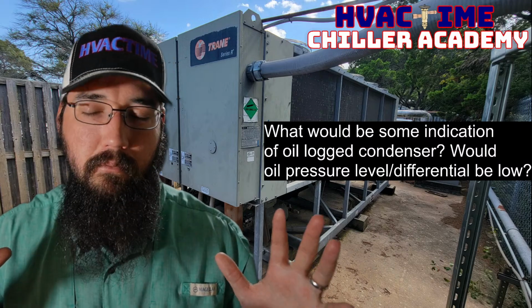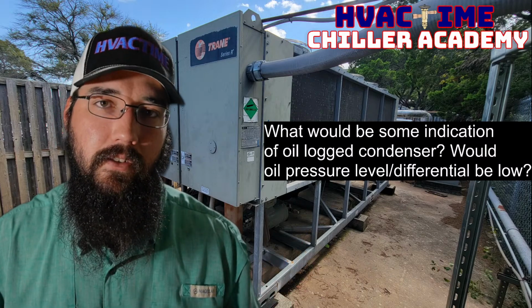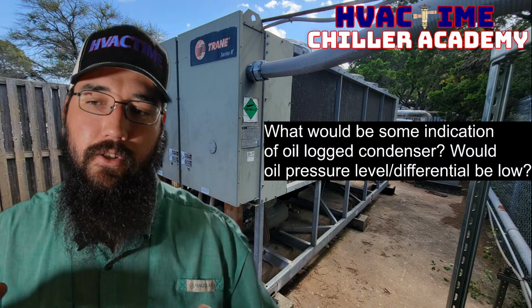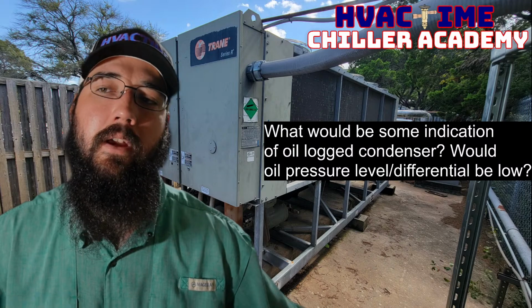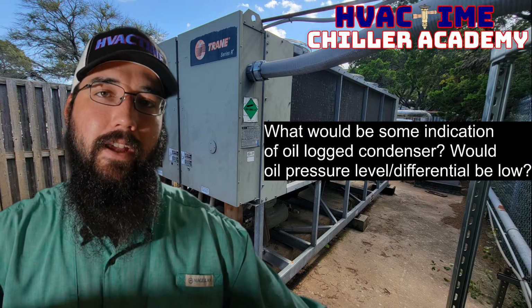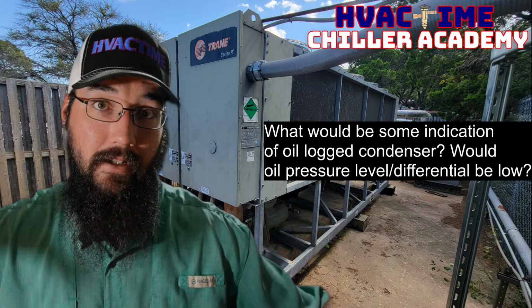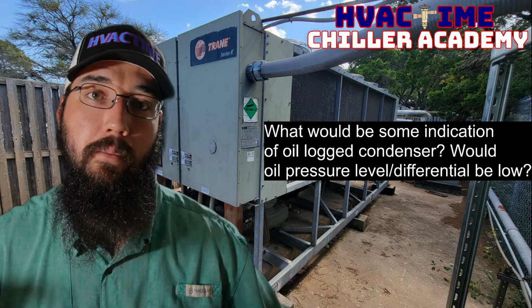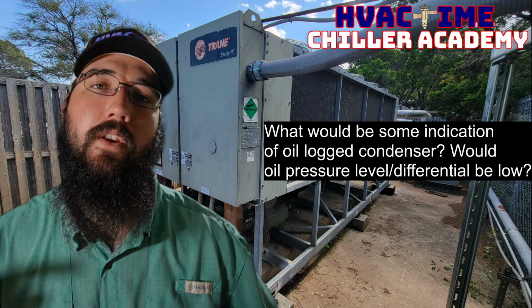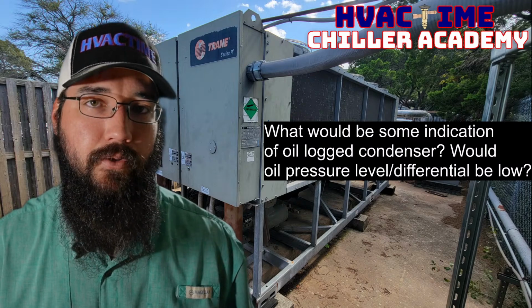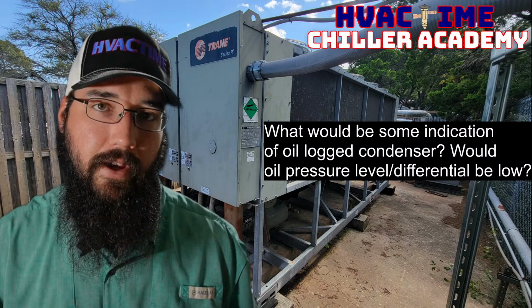And in my experience, it's high oil charge. There's too much oil in the system, and it's allowing that oil to get congregated and collected in mass in the wrong places in the system, more than the system was designed to overcome naturally on its own, which is going to affect your heat exchange.